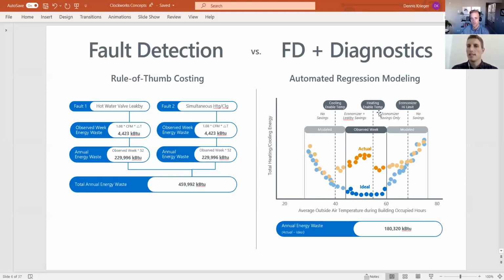When does my heating system enable, and what does that mean for my leak-by savings? I can't count leak-by cost savings during times when my boiler plant isn't on. Simple things like that are incredibly difficult to handle when you're building them into each individual rule—it's much easier in a holistic set of algorithms that account for the building profile as well as the unique conditions detected in the equipment itself.